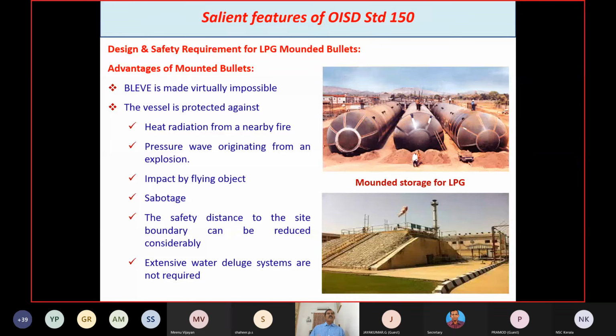This will be totally impossible with a mounded bullet, because the bullet is fully covered by earth. So this is the advantage. Now PESO also recommends only mounded bullets instead of spheres, so hereafter mounded bullets will be coming up. The vessel is protected against heat radiation from nearby fire. The pressure wave from an explosion will not affect it, impact by flying objects will not affect the bullet, and sabotage will not be possible. The safety distance to the site boundary can also be reduced considerably.